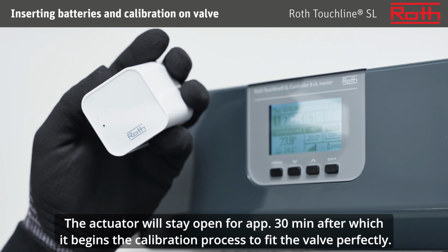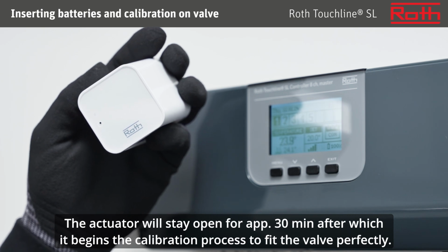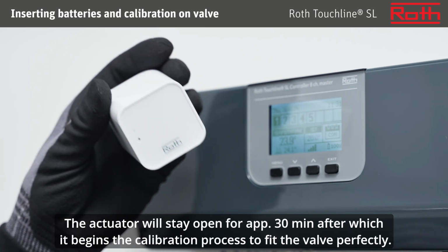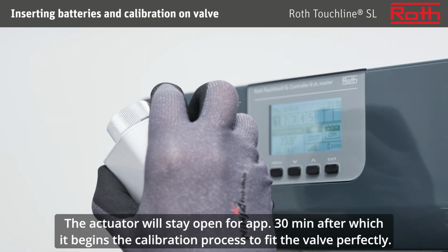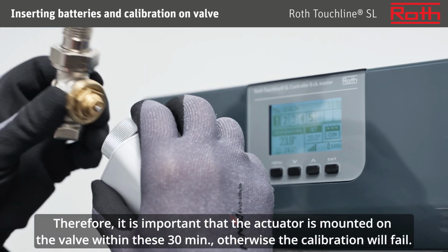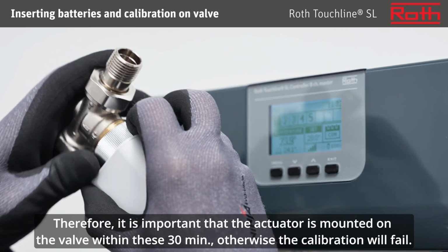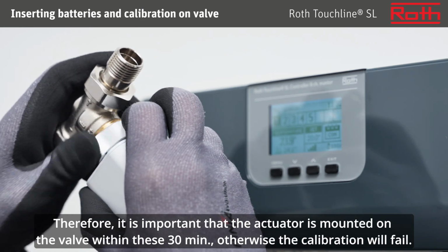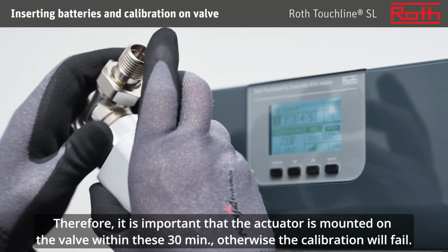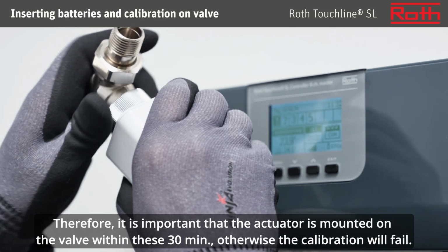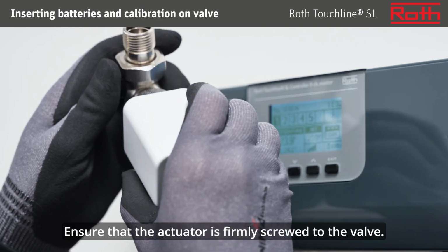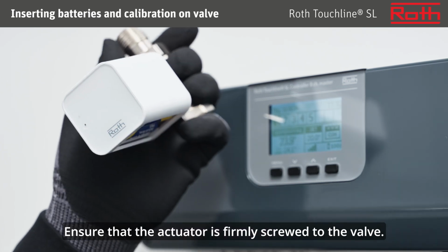The actuator will stay open for approximately 30 minutes, after which it begins the calibration process to fit the valve perfectly. Therefore, it is important that the actuator is mounted on the valve within these 30 minutes, otherwise the calibration will fail. Ensure that the actuator is firmly screwed to the valve.